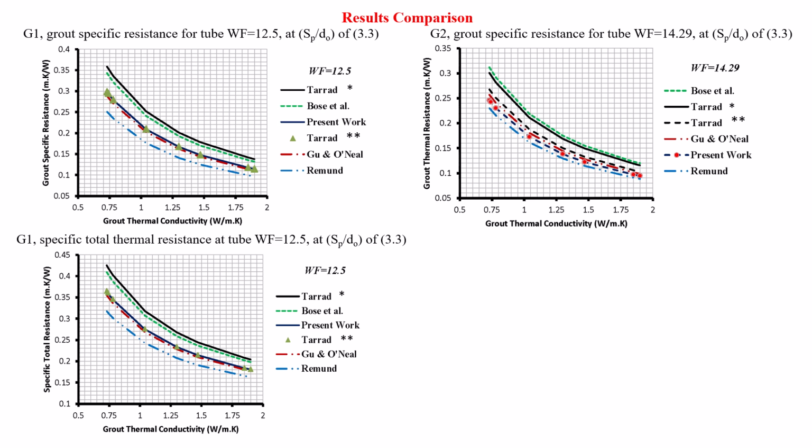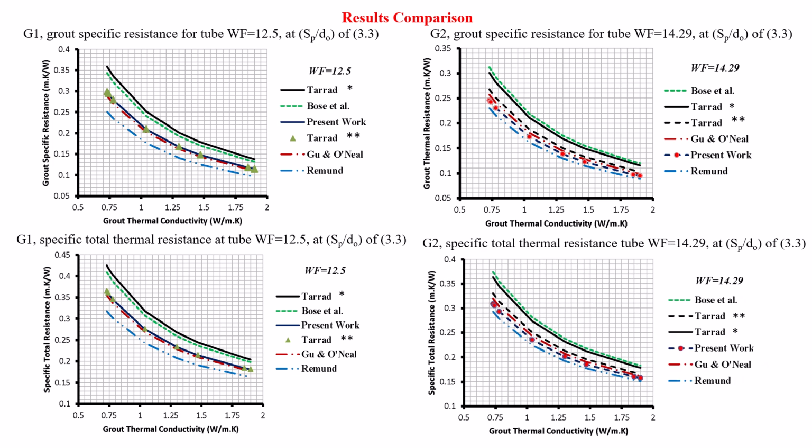The total resistance has been calculated for both geometries, and of course these values should be used to predict the depth and the length of the heat exchanger, which can be used to achieve a certain cooling load, which represents the condensation load for the refrigerant Freon 410A, which mainly depends on the total heat transfer rate and the temperature difference between the fluid and the soil which surrounds the borehole.